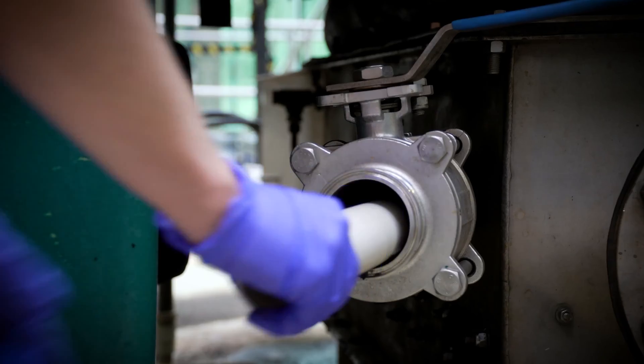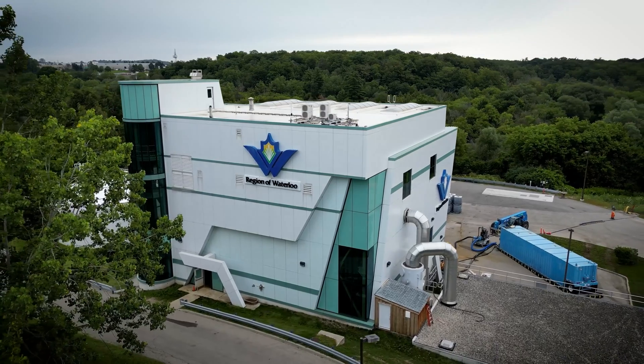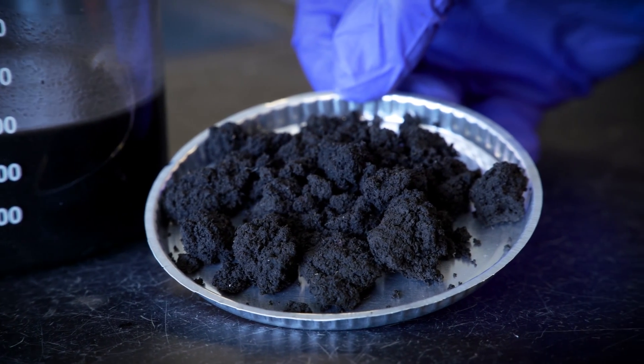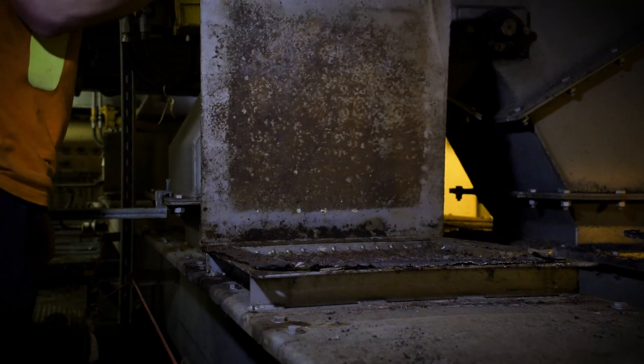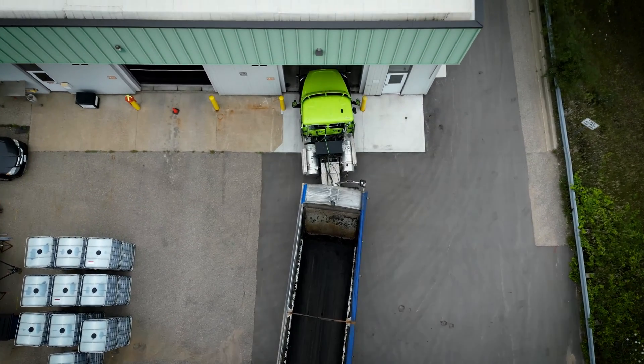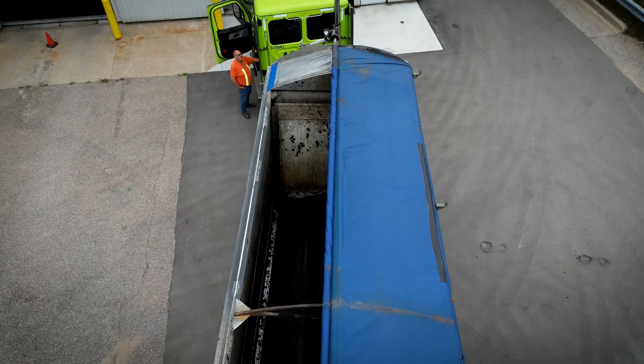The sludge is now a dark, wet, soil-like solid we call biosolids. On average, 73 tons of biosolids are taken off-site each day. The biosolids are ready to use as a product only after following strict treatment and testing to meet provincial regulations. An auger system moves the biosolids from the centrifuge area to one of the three hopper bins, which provide temporary storage until ready for loading onto a transport truck. When the truck arrives, it enters the loading area and stops so the truck bed is underneath the four discharge chutes to be filled with treated biosolids. The auger system pushes the biosolids from each hopper bin and into the truck bed.